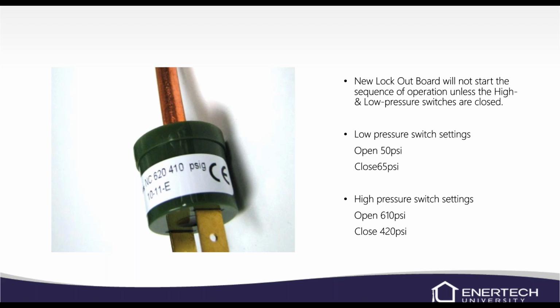It'll wait 5 minutes, it'll try again. If that switch is still open, it'll lock it out. After that 3rd time, it'll go into a hard lockout. I will make a quick note. If you have the unit in test mode and the low or high pressure switch is open, the soft lockout, your first 2 lockouts are considered the soft lockout. Those will happen so fast in test mode, you won't even see it happen, and it'll almost immediately go into a hard lockout where it has to be reset.